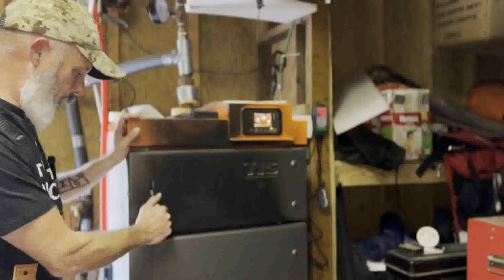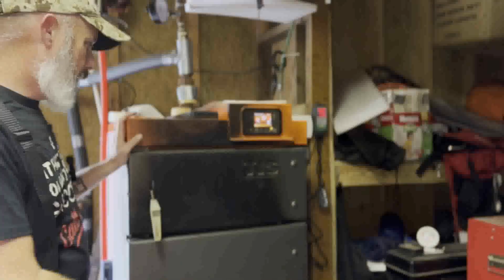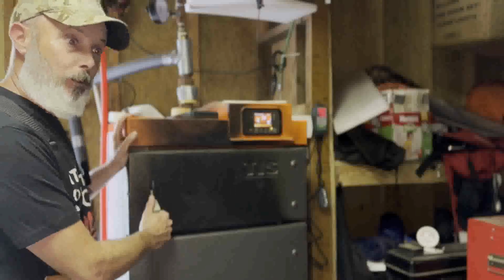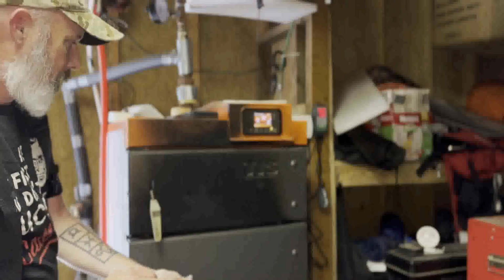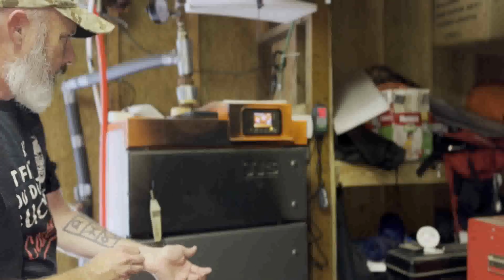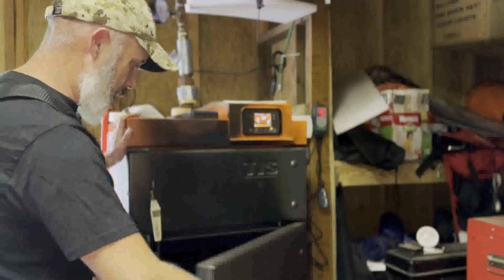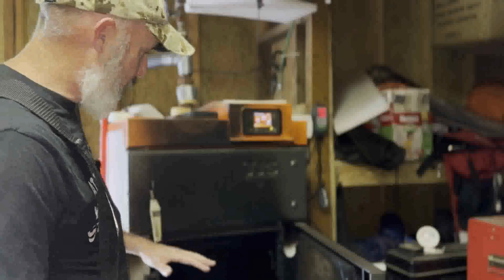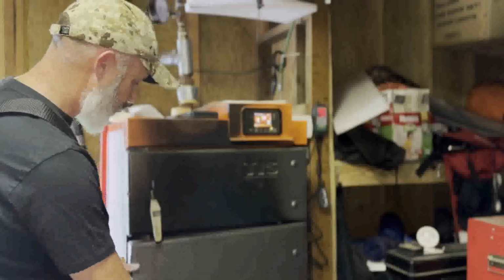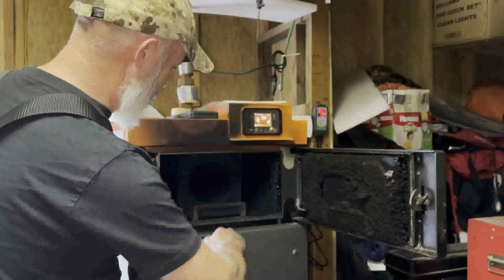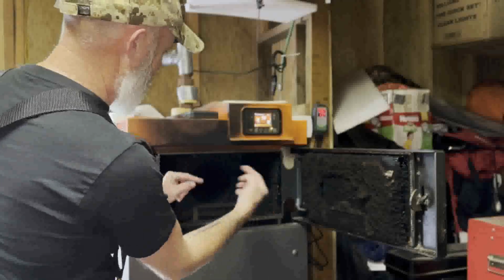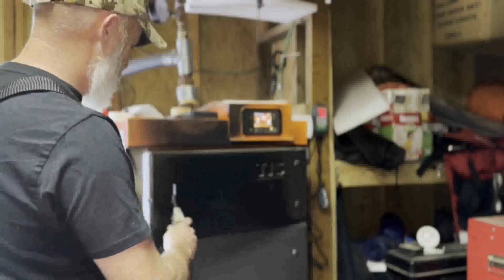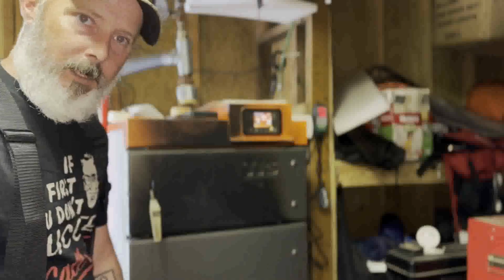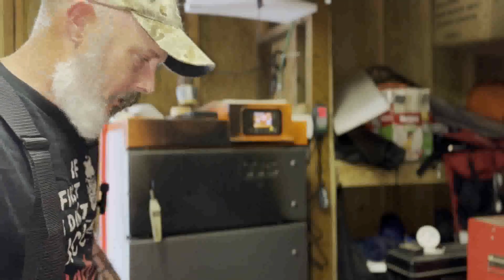This is the Uni-15, UNI-15. It's made by a company called Hydronics. They're out of Belarus, so I did get this before all of the Ukraine stuff was going on. But yeah, so basically you have a burn chamber here, and I'm going to bring you a close-up view in just a little bit. Burn chamber. That's where you would load your firewood. This is a clean out where it comes up. The flue gases go up in and around a couple of tubes and passages, comes up and in here. This is all surrounded by water. In the very bottom, which you won't see in this camera angle, is your ash and your ash clean out.